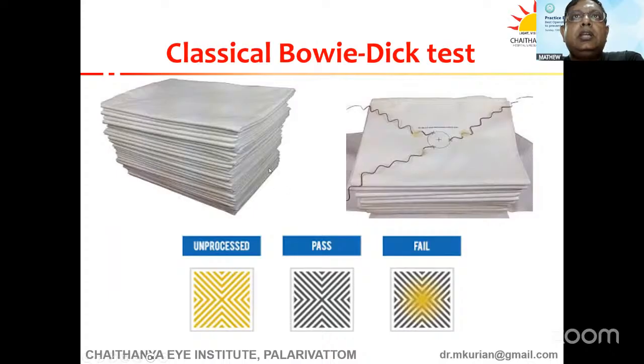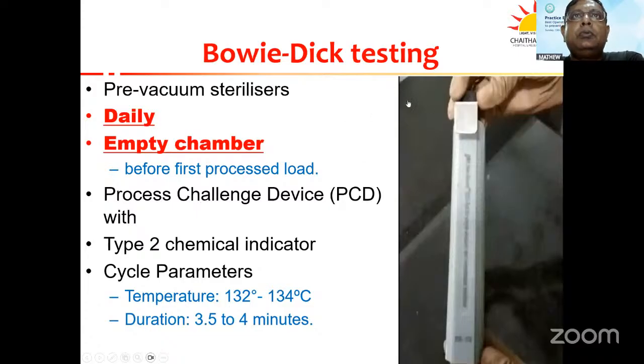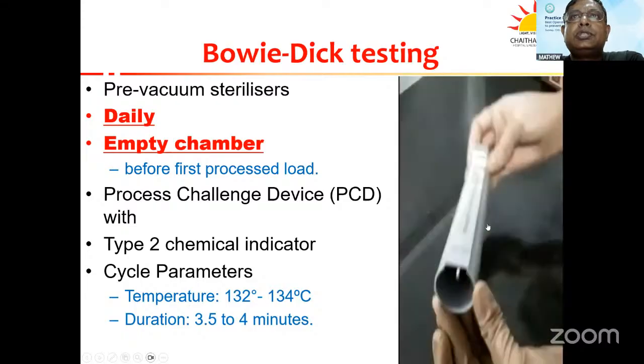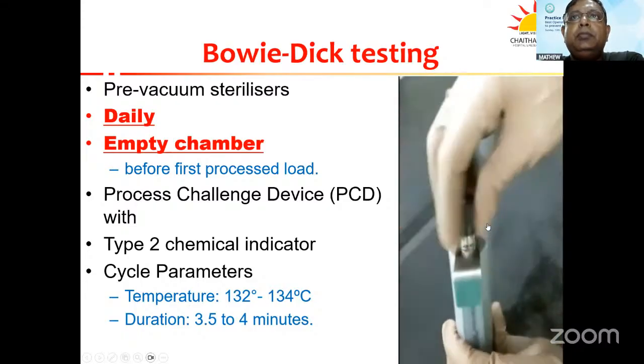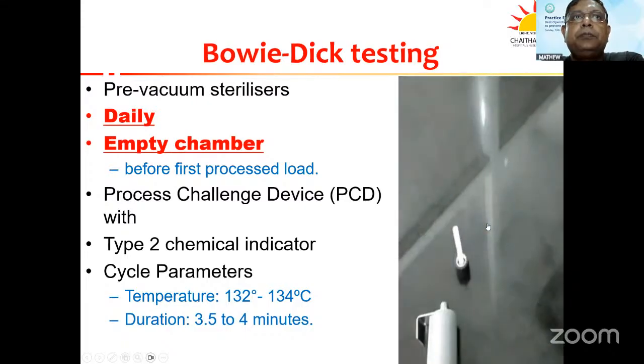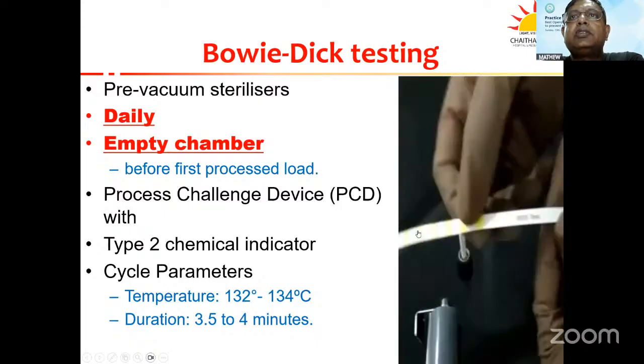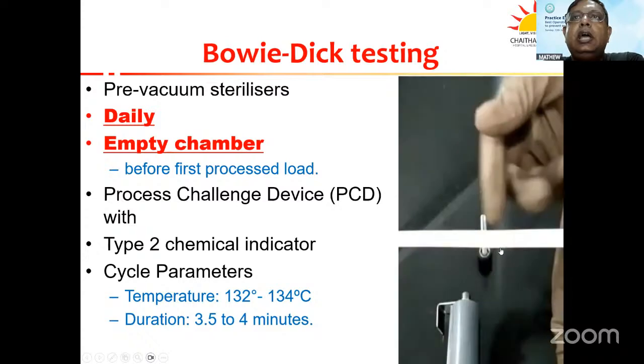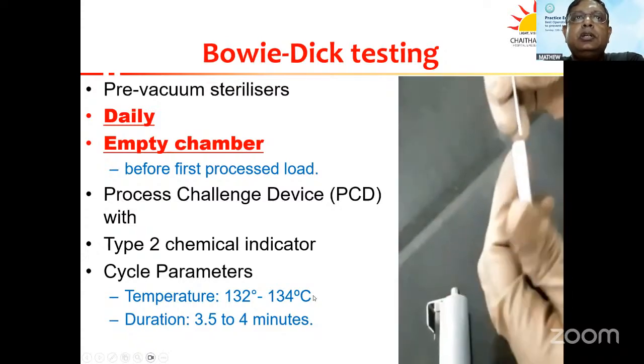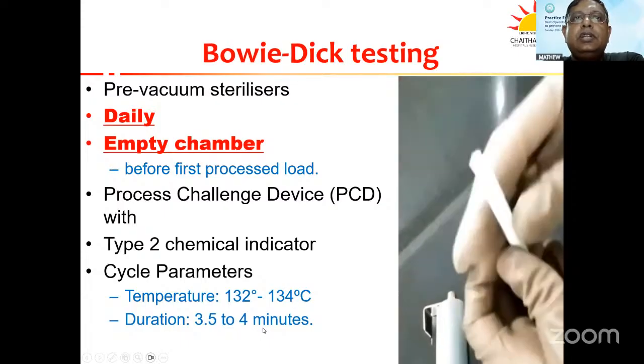In autoclaving, the classical Bowie-Dick is this layers of cloth where you put the large sheet, which is yellow in color when it is unprocessed, and when it passes this process, it will become all black, and a failure would be indicated by a little bit of yellow, and the rest of it is still black. But that is a little more cumbersome. And what we do now is to have this kind of a Bowie-Dick process challenge device. We do it every day in the empty chamber of the autoclave before the first process load for that day. And this is the Bowie-Dick strip. It is all yellow when it is unprocessed. And we keep it for the temperature 132 degrees to 134 degrees for a duration of 3.5 to 4 minutes.